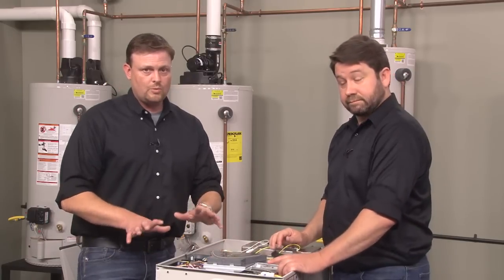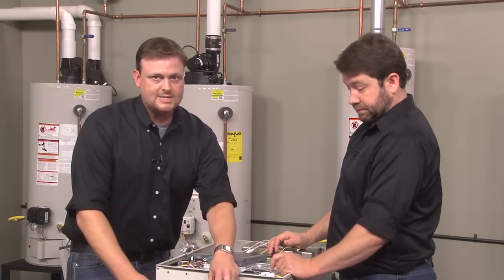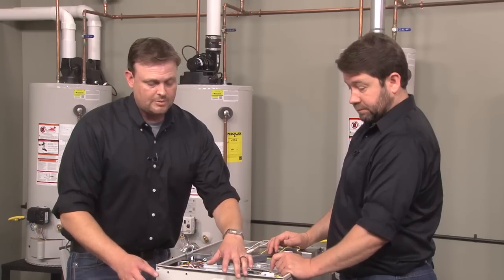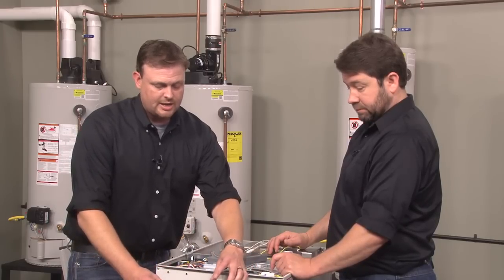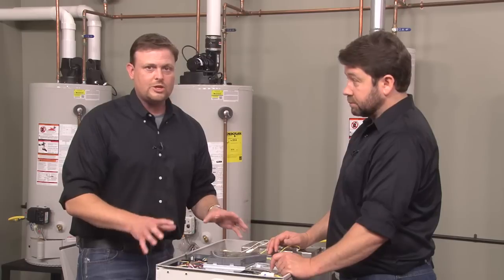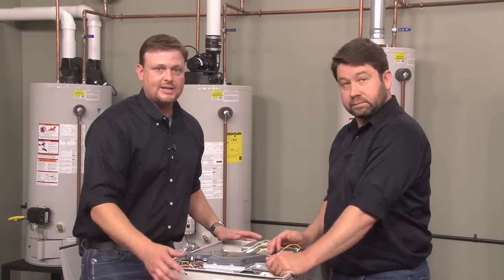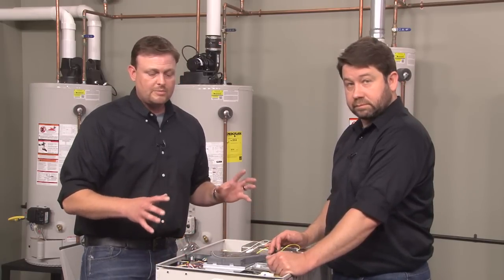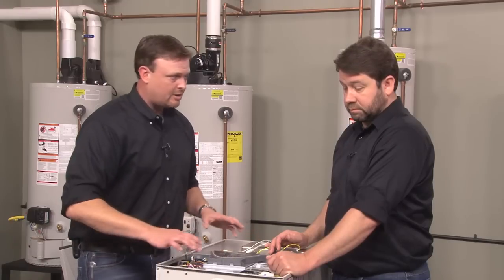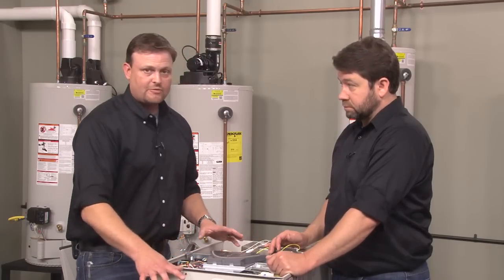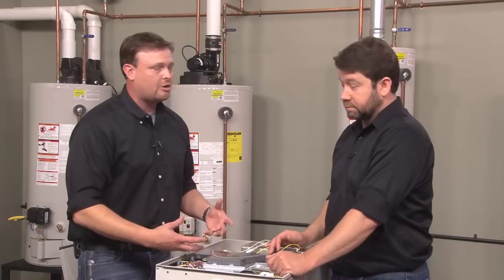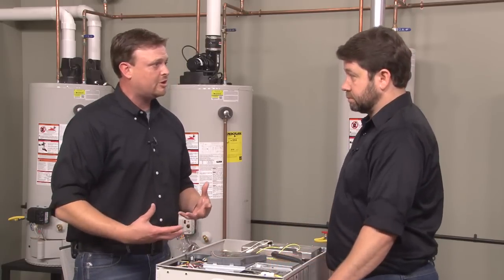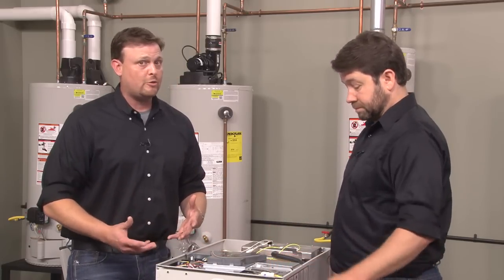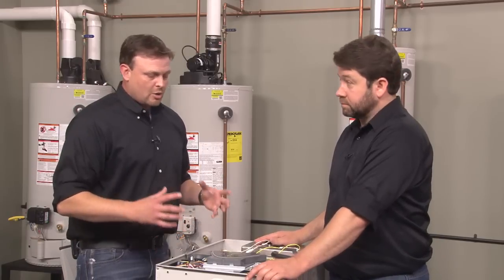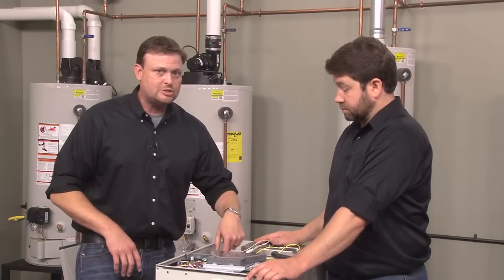Where we're going to hook up, we're using these isolation valves, the isolation kit. You can go ahead and hook your lines up. You still have water connected and all of that, you haven't valved off the unit yet, so you're going to turn the unit on. You're going to run it up to 140 degrees and keep that running for about 1 to 2 minutes. The whole reason is we're trying to close the bypass.